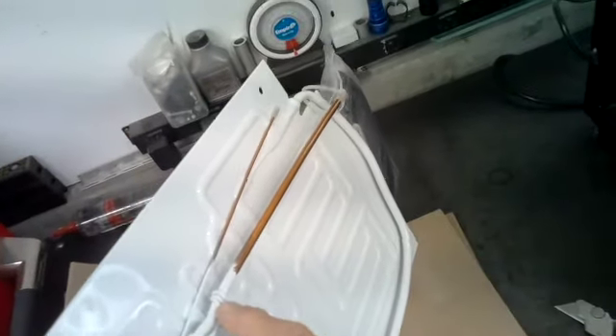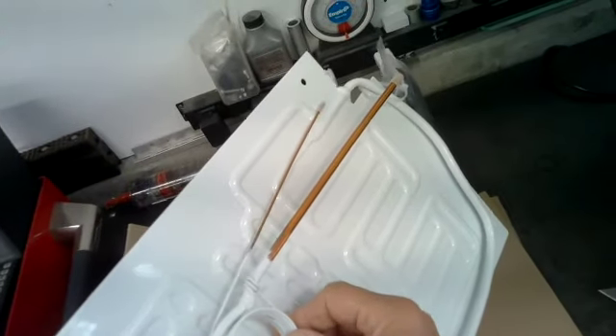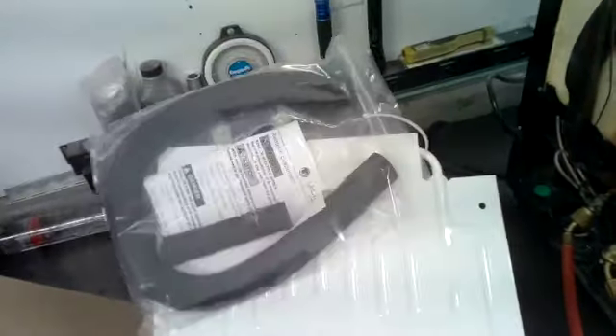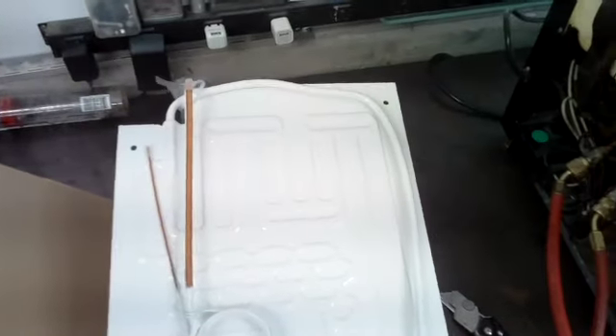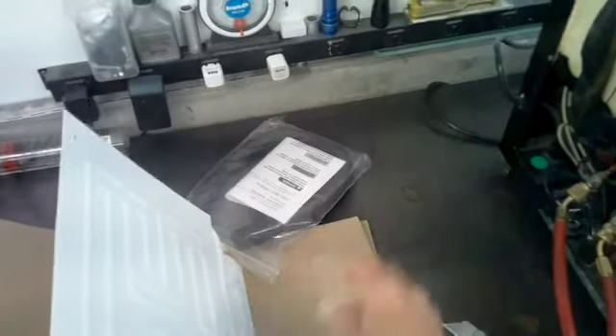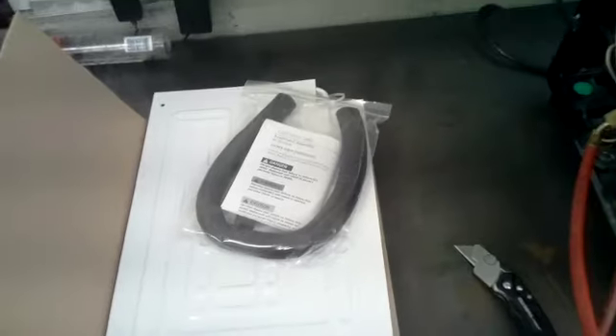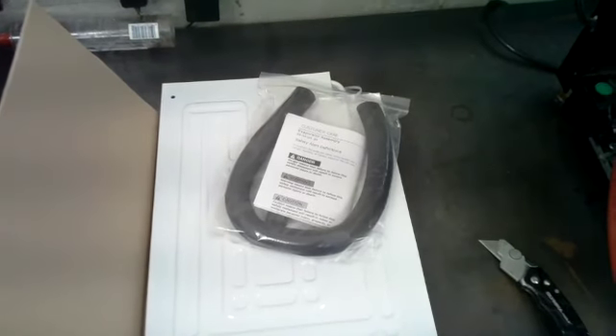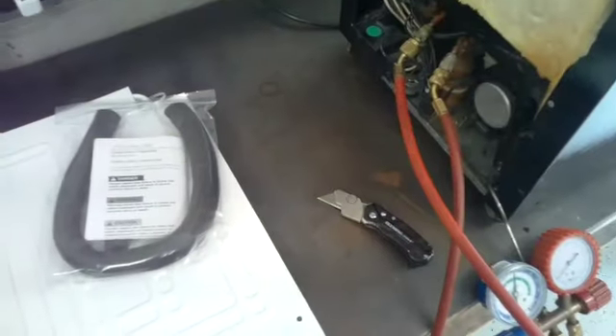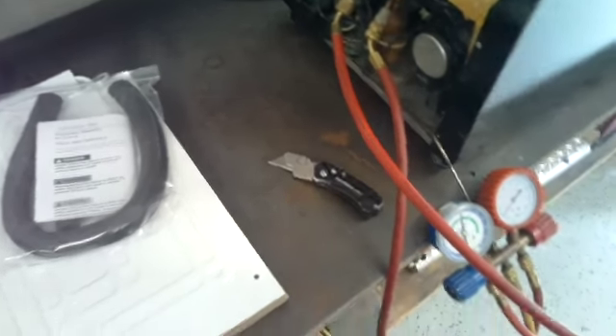So here's the heat exchanger. See? It's attached to the suction line right there. Now I don't know. There's a big difference between here and there. So what we're going to have to do is find the U-line wine cooler that this evaporator goes to, check the compressor. We know it's the refrigerant R134A. Check the compressor size and see if it's pretty close to what we already have in there, and then we will adapt this evaporator plate to this Sub-Zero wine cooler and see how that works. So once again, stand by.